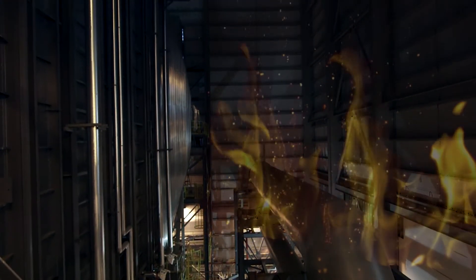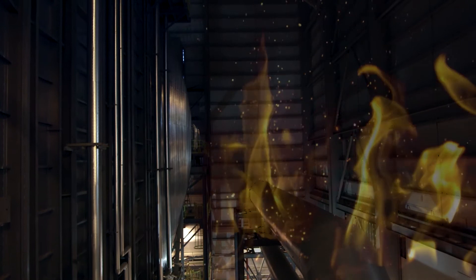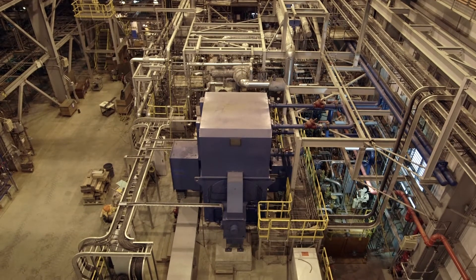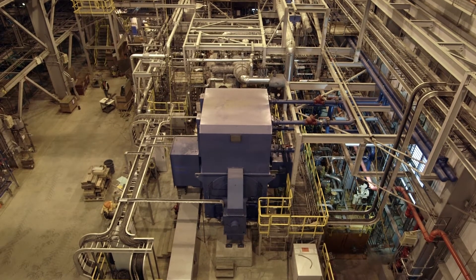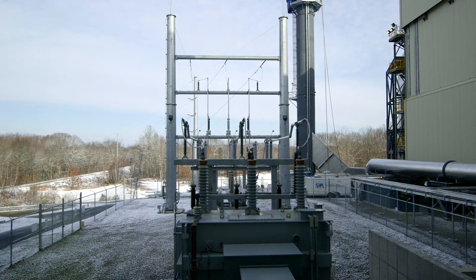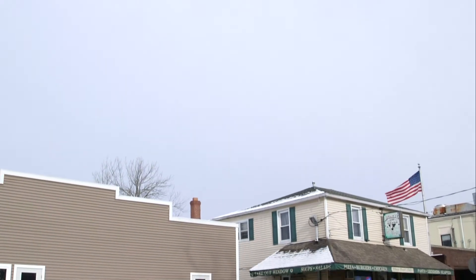The burning wood is fanned by air ducts and superheats to over 950 degrees, creating steam at over 1,550 psi. The pressurized steam expands as it drives a turbine in the main power generator. The Plainfield site produces a net 37.5 megawatts to a local substation in the town of Plainfield, and then to the grid, powering as many as 37,000 homes and businesses.